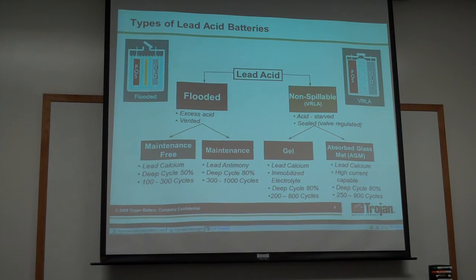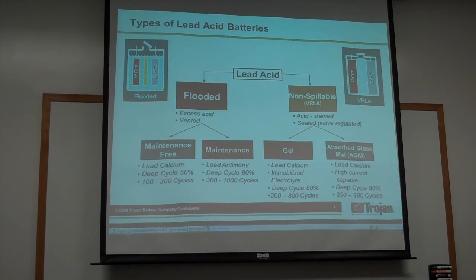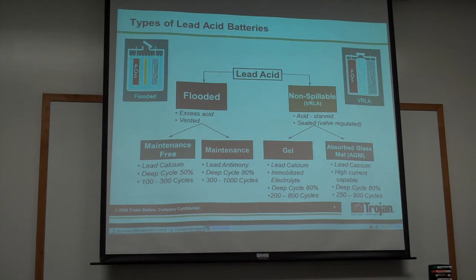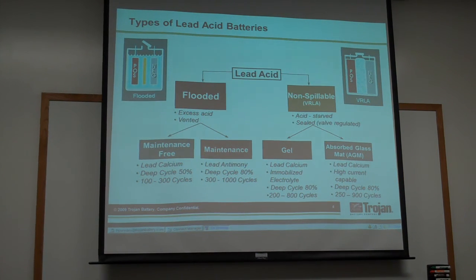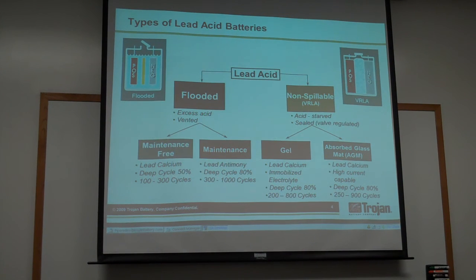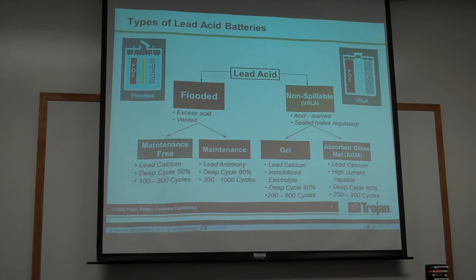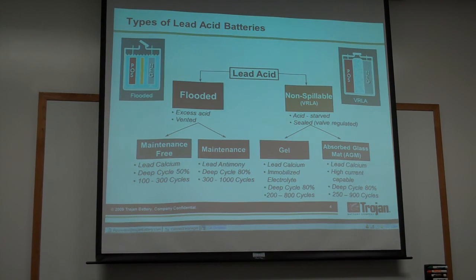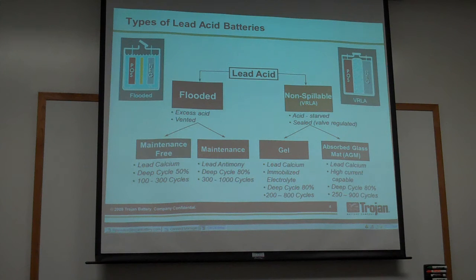There are two broad categories in lead acid batteries. One of them is a flooded, vented battery, where the electrolyte is mobilized. And then the second type is what is commonly called a sealed battery, where the electrolyte is immobilized. Within the sealed world, you have a type of battery called an AGM, and then a gel battery. Both of those are sealed batteries. The AGM stands for absorbent glass mat, and in the case of the gel battery, it's called a gel battery because the electrolyte is gelled with a combination of silica.